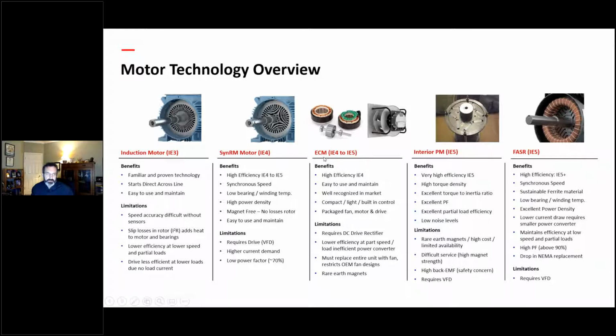So really, electrically commutated motors, which is really a DC permanent magnet motor, interior permanent magnet motors and this motor that we're talking about here all add magnet material to reduce the losses in the stator and get you to higher efficiency. Synchronous reluctance motors do it all just with basically active material in the stator and a no-loss rotor. So it's good, except active material means the motors are typically larger. All of these from the left over, except induction, require a drive, but they have lower power factor, something like 70%. You have to run it on a drive, so what you're seeing from a power factor standpoint ahead of the drive is still very good, but the low power factor of the motor means that motor typically draws more current. And if it draws more current, it's a larger, heavier motor than typically these over here.